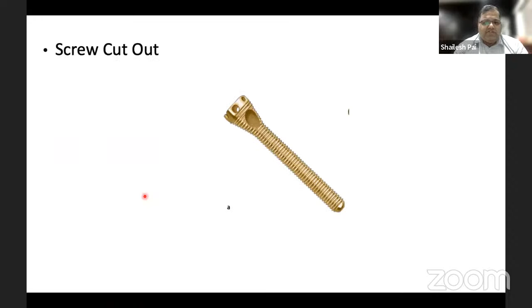The cutouts, again, which was the issue with the previous generation nail, have now been countered with this screw-in-screw design. So this screw is tangential at 30 degrees to the first screw. The first golden screw goes through the nail. The second screw goes through the first screw, outside the nail, and takes some purchase in another part of the humeral head. And this trajectory is fixed at 30 degrees. So any physiological force which is perpendicular to this screw is not perpendicular to the second screw at the same time, and hence it provides a significant cutout resistance.